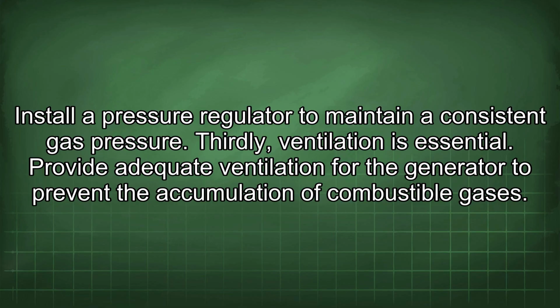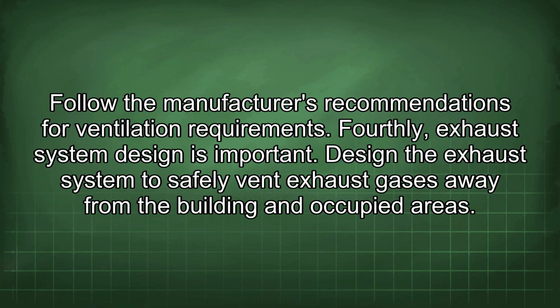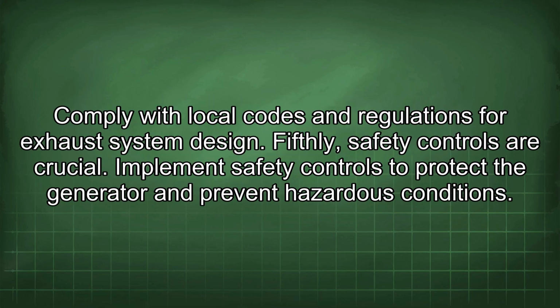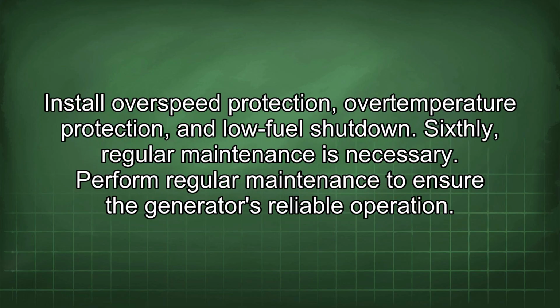Thirdly, ventilation is essential. Provide adequate ventilation for the generator to prevent the accumulation of combustible gases. Follow the manufacturer's recommendations for ventilation requirements. Fourthly, exhaust system design is important. Design the exhaust system to safely vent exhaust gases away from the building and occupied areas. Comply with local codes and regulations for exhaust system design. Fifthly, safety controls are crucial. Implement safety controls to protect the generator and prevent hazardous conditions. Install overspeed protection, over-temperature protection, and low fuel shutdown.